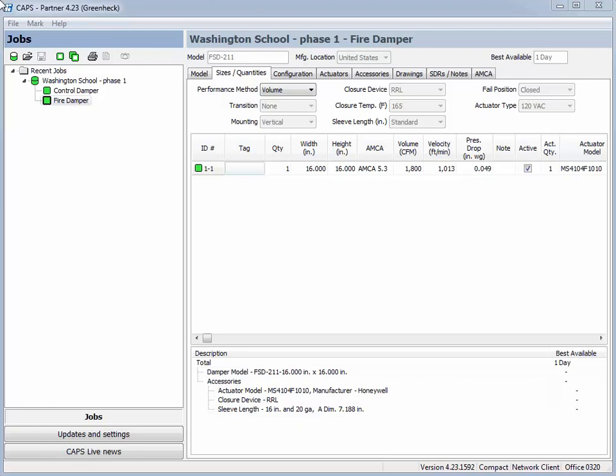First, you will need a completed CAPS job. My example will use the 1.5 hour rated combination fire smoke damper, model FSD211. It is 16 inches wide by 16 inches high, selected at 1800 CFM.